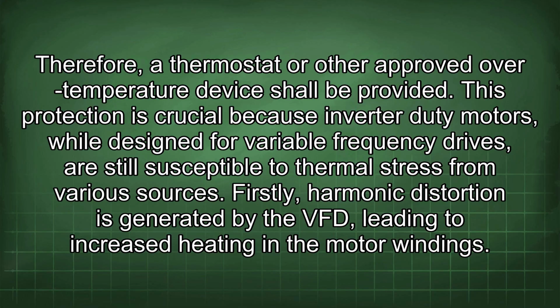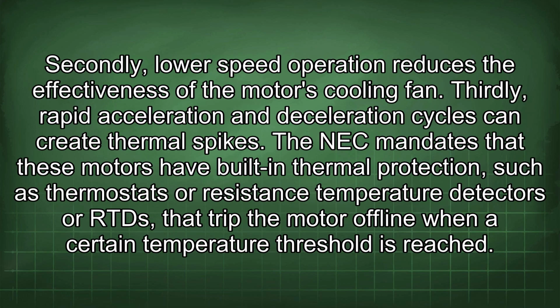This protection is crucial because inverter duty motors, while designed for variable frequency drives, are still susceptible to thermal stress from various sources. Firstly, harmonic distortion is generated by the VFD, leading to increased heating in the motor windings. Secondly, low speed operation reduces the effectiveness of the motor's cooling fan. Thirdly, rapid acceleration and deceleration cycles can create thermal spikes.